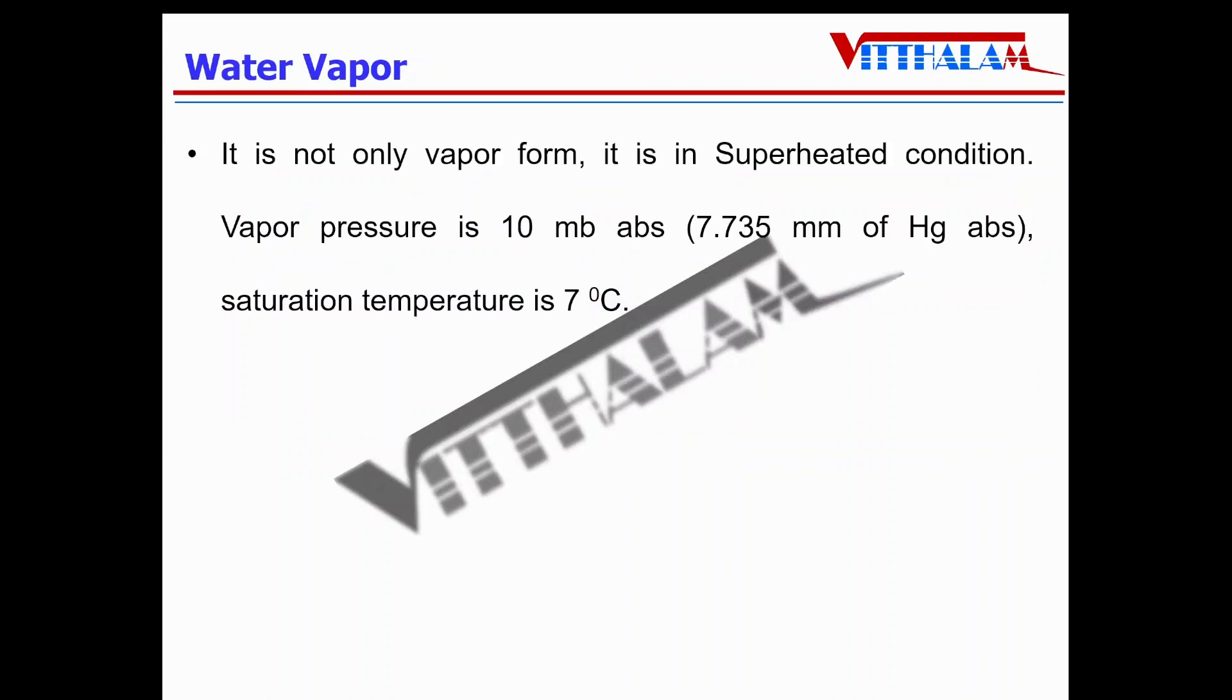Apart from that, water is not only in vapor form, it is in superheated conditions. Because at 10 millibar, that is 7.735 mm of Hg absolute, saturation or we can say boiling point or boiling temperature of water corresponding to that pressure is 7 degrees Celsius. It means above 7 degrees Celsius, water will always be in superheated conditions.